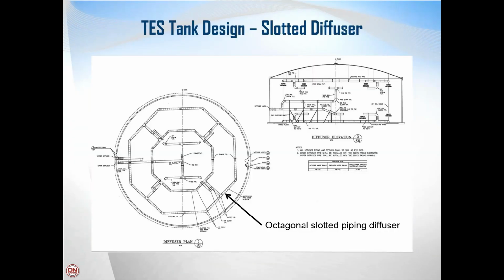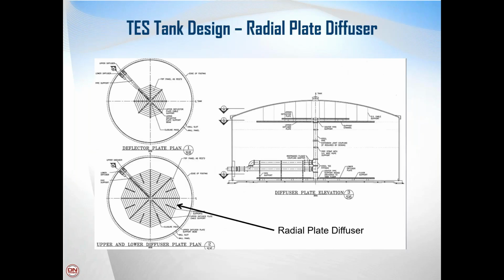Just a little bit about the design of our thermal energy storage tanks. As I mentioned, we specially designed the diffuser type piping inside of the tank. And this specially designed piping allows the chilled water to slow down as it enters and leaves the tank so that it's near laminar flow and doesn't mix up the cold water at the bottom of the tank with the warm return water at the top of the tank.